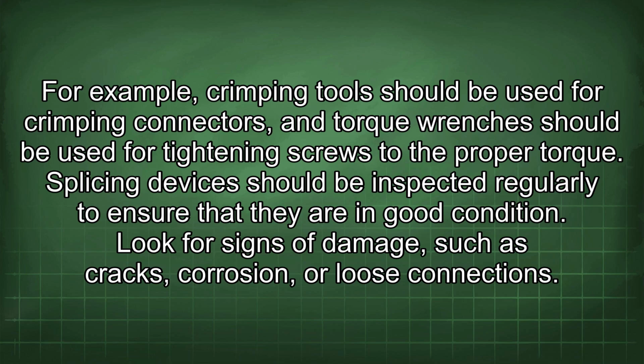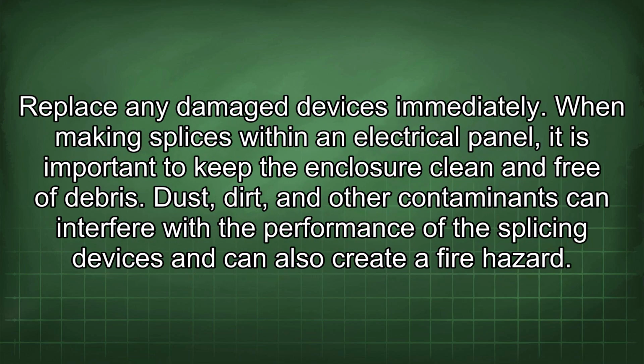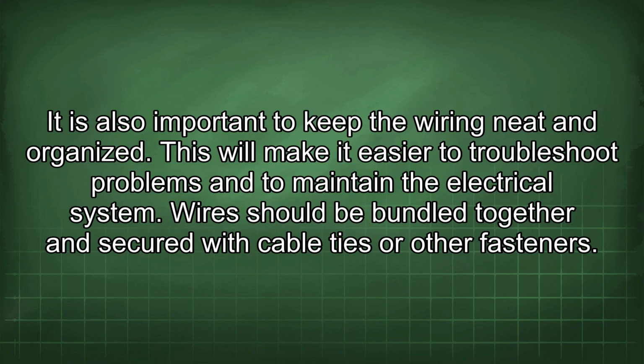the proper torque. Splicing devices should be inspected regularly to ensure that they are in good condition. Look for signs of damage, such as cracks, corrosion, or loose connections. Replace any damaged devices immediately. When making splices within an electrical panel, it is important to keep the enclosure clean and free of debris. Dust, dirt, and other contaminants can interfere with the performance of the splicing devices and can also create a fire hazard.